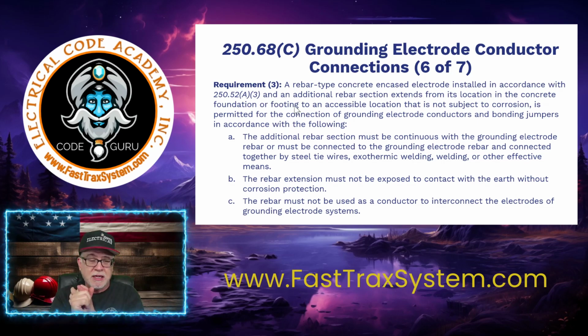So y'all remember, it has to be either half-inch rebar, 20 feet of it, in the footer or foundation, encased in 2 inches of concrete. It has to be in contact with the earth.